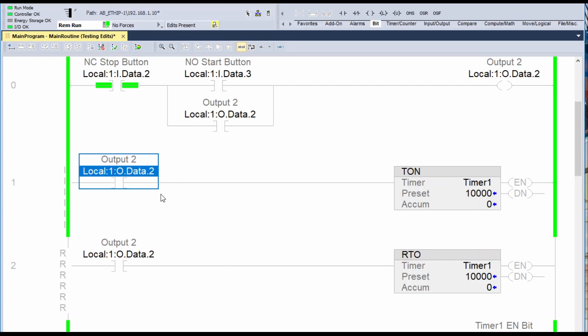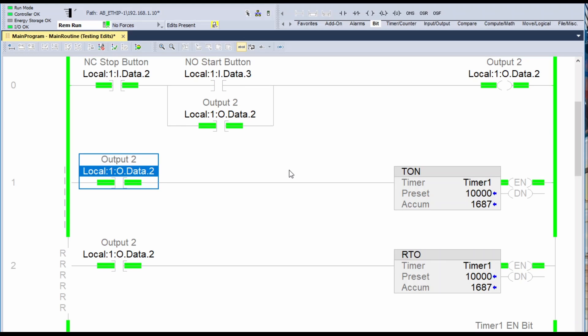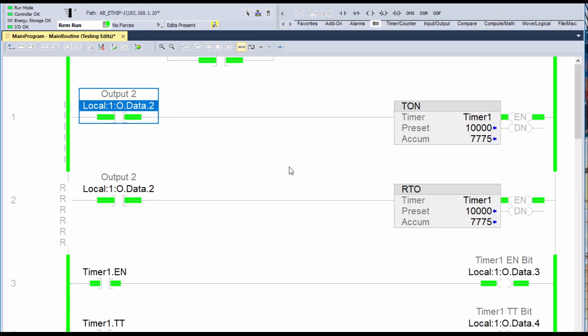I'm just going to test out my program here. This is my stop push button, I'm going to hit the start push button — that's going to turn on the output, this will latch the output on, and then this will be true and turn on my timer. So there's my timer timing out, going up to 10 seconds. We can see the associated bits are live — the enable bit is live and the TT bit was true. Now we have the preset equal to the accumulated value.